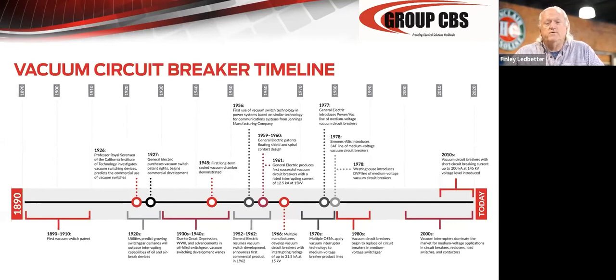So what happened was, when people started specifying new equipment, obviously they specified the vacuum breaker, and the air breaker quickly went away. Now, the air breaker did stay and is being used today in certain marine applications and nuclear applications, where it is a certified product and where the vacuum breaker is not certified. So there are still a few air breakers built across the world, but very few. So in the 70s and 80s, it immediately switched to where 90% of the new equipment was vacuum breakers.